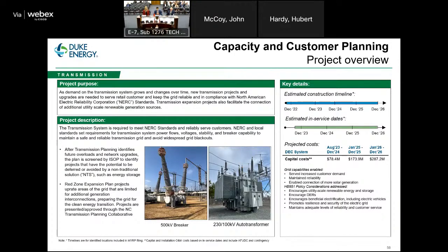The last area I'll mention is our red zone expansion plan, or transmission expansion plan, or our red zone project. So again, I know the commission is familiar with these from the carbon plan proceedings, but these are areas of the grid where we have had numerous interconnection requests for new solar generation. And our interconnection studies have identified that these transmission circuits are at or near maximum capacity. They're not able to connect additional generation of significant magnitude without significant upgrades. So reconductoring large portions of the system. So we actually have 4 transmission circuits included in our multi-year rate plan that are in a red zone in the DEC area, which is actually the South Carolina service territory of our Duke Energy Carolinas location. And I'm going to talk about a specific one of those on the following slide.